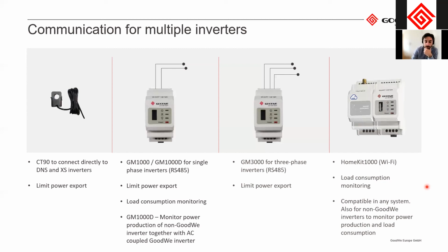It's possible to connect it to only a household or residential system where you just monitor the load. And then after a year, for example, knowing the load, then you can install the correct inverter and the PV sizing. Or it can be used in combination. Let's say there's already an existing inverter and then you want to add a battery inverter, then you can, for example, use this one. We are also launching soon a 3-phase HomeKit for three-phase, which will then also be useful in some residential applications.